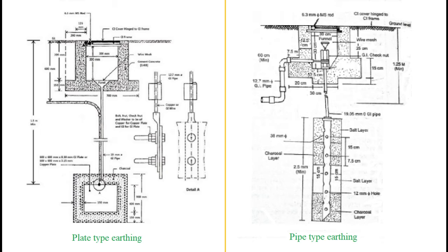In case of plate type earthing, a 2 feet by 2 feet pit is dug to about 1 meter depth. Initial layers of salt, coal and soil are placed at the bottom of the pit. The copper or lead plate, about 1 feet by 1 feet, is placed on these layers. This plate is firmly attached to a thick copper wire using nut, bolt and washer, or it might be welded to the plate. This wire is taken away through a pipe to reach the bottom of a chamber constructed to keep the earth point in protected form. Above this plate, layers of salt, coal and soil are placed successively.